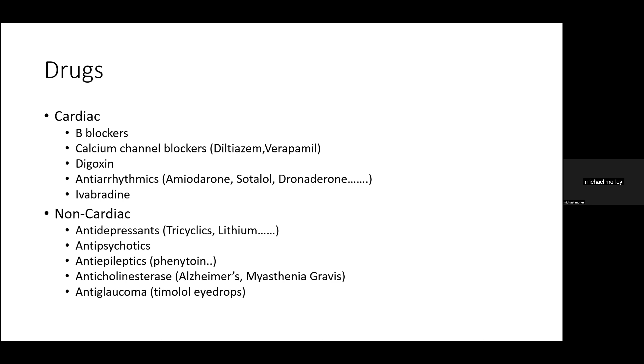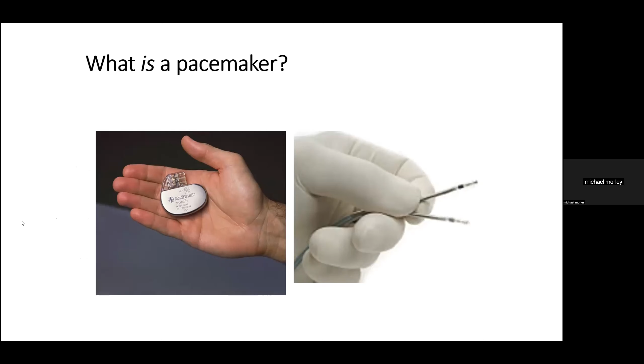So we move on now to permanent pacing. A permanent pacemaker is really just a slightly more sophisticated version of our temporary pacing system. It consists of a pulse generator, which is a titanium box containing a battery and some electronic circuitry with a plastic header which allows for the connection of the leads. Battery life on a typical pacemaker these days is somewhere between 10 and 15 years.